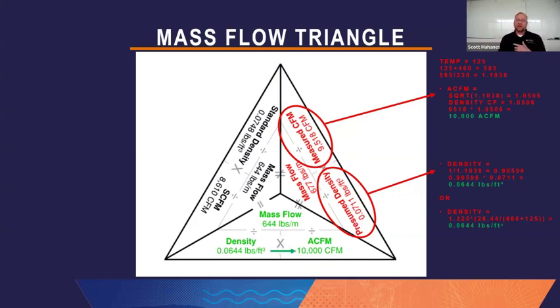You multiply the two together, you get 644 pounds per minute. You can transfer that over to the standard density side, divide it by standard density, and then you get that SCFM value. And so what's interesting here is I'm really not moving 10,000 CFM at the fan inlet.